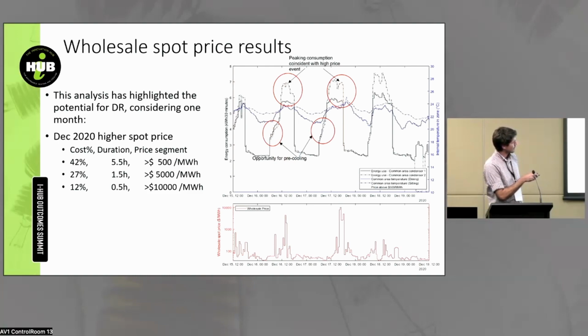What we saw when we looked at the concurrent condenser usage was that, with no demand response, there were quite a few times when air conditioners were running flat chat at the same time that there was a very high wholesale spot price. So what that tells us is that there are periods of peaking consumption which coincide with a high spot price event - an opportunity to essentially turn off the air conditioners for that period. But there's also a concurrent opportunity to pre-cool the space if you have predictive forecasts: pre-cooling in the morning and then turning the air conditioners off during the high price events.